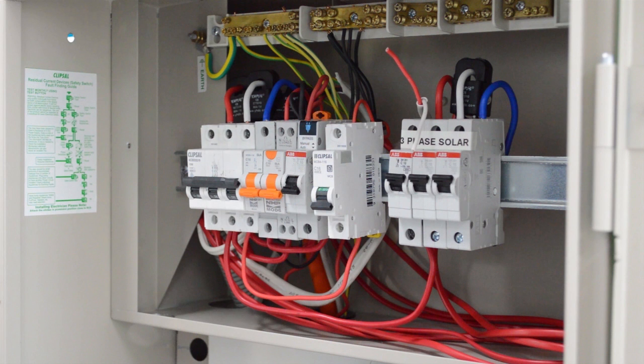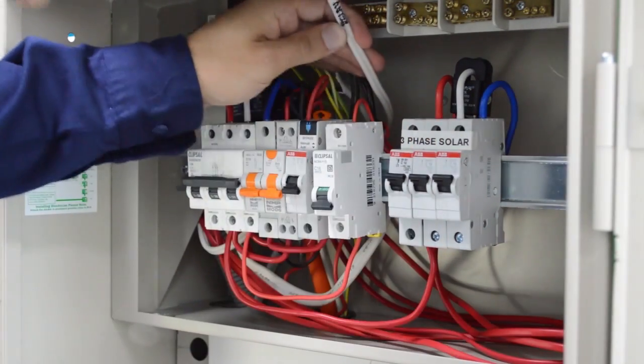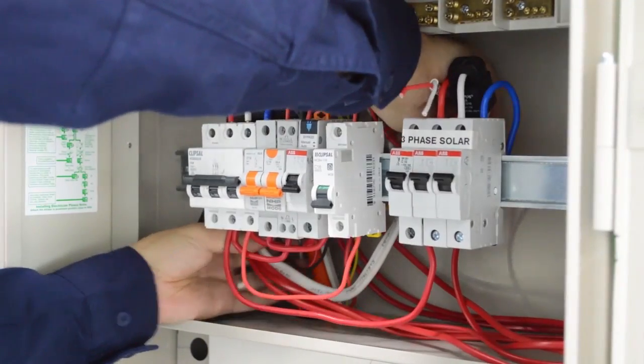Once a suitable circuit has been identified and the owner agrees to have it switched, you can proceed. Bypass switches must be installed for each switch in parallel. To start, we're going to run a suitably sized twin active, 1 of these per switch and 1 per bypass switch if using an external weatherproof switch as a bypass switch. For the first demonstration, I'll be demonstrating with an external weatherproof bypass switch. So I've run 2 cables, twin active 2.5mm, or suitably rated for the circuit being switched.